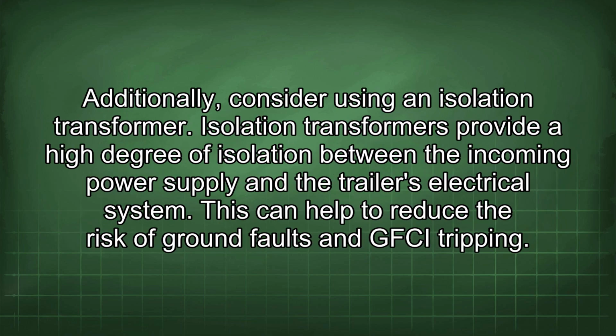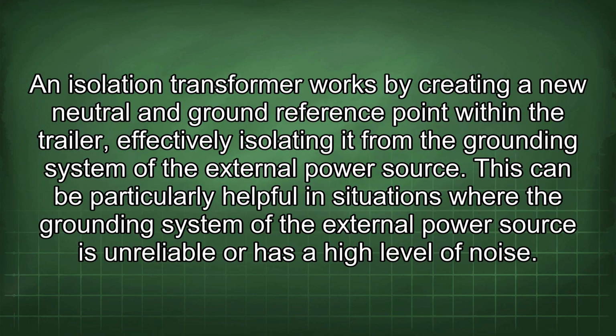Additionally, consider using an isolation transformer. Isolation transformers provide a high degree of isolation between the incoming power supply and the trailer's electrical system. This can help to reduce the risk of ground faults and GFCI tripping. An isolation transformer works by creating a new neutral and ground reference point within the trailer, effectively isolating it from the grounding system of the external power source. This can be particularly helpful in situations where the grounding system of the external power source is unreliable or has a high level of noise.